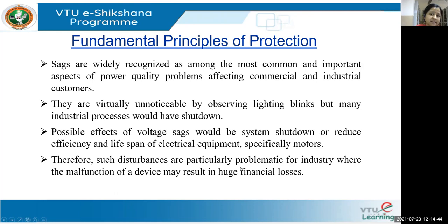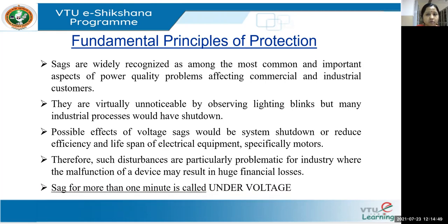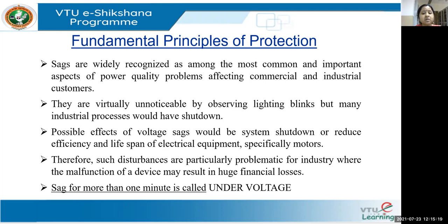Any sag which persists for more than one minute is defined as an under voltage. It is important to understand what under voltage means — it's not just about the magnitude being below a nominal value; it's also about the duration, how long the voltage sag persists. If the sag persists for more than one minute, it is defined as an under voltage, which is a serious issue for large industrial customers.